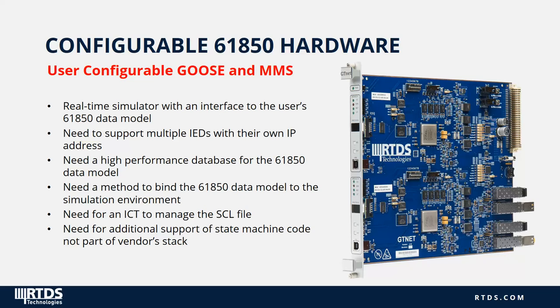User configurable GOOSE and MMS. The hardware shown on the right is a picture of the GTNet card. The real-time simulator has an interface to the user's 61850 data model through the GTNet hardware. You need to support multiple IEDs with their own IP address, a high-performance database for the 61850 data model, and a method to bind the 61850 data model to the simulation environment. There is a need for an ICT to manage the SCL file, as well as additional support for state machine code and logics not part of the vendor stack.